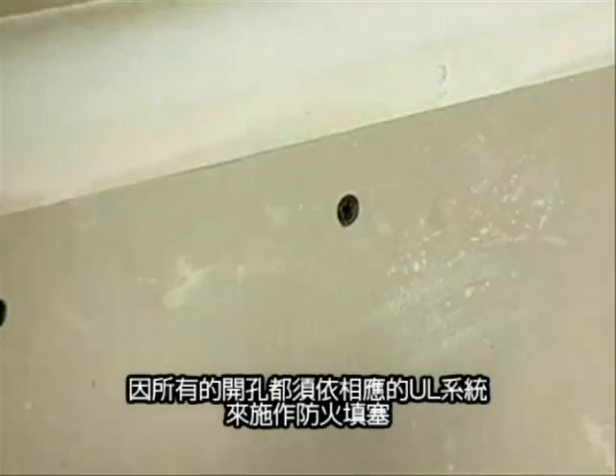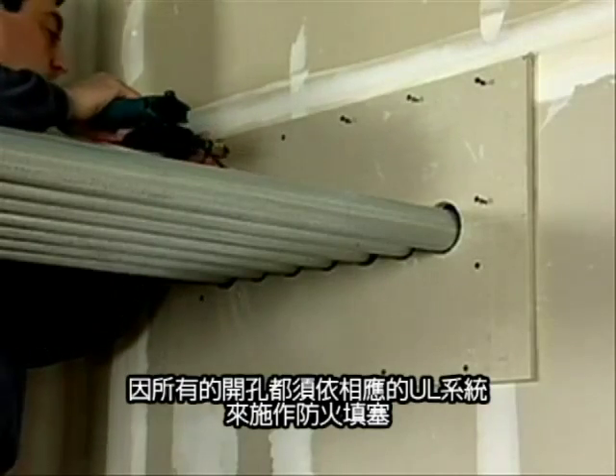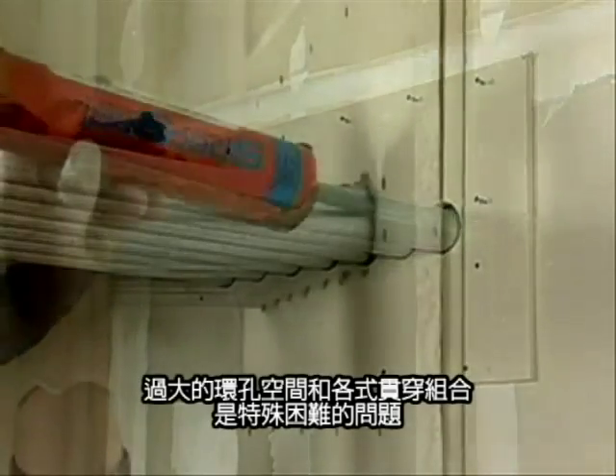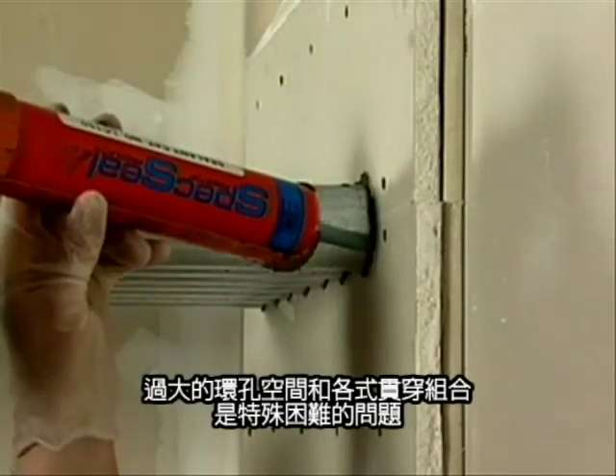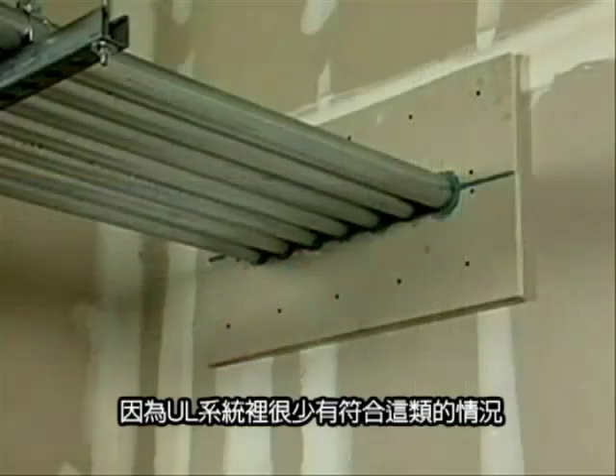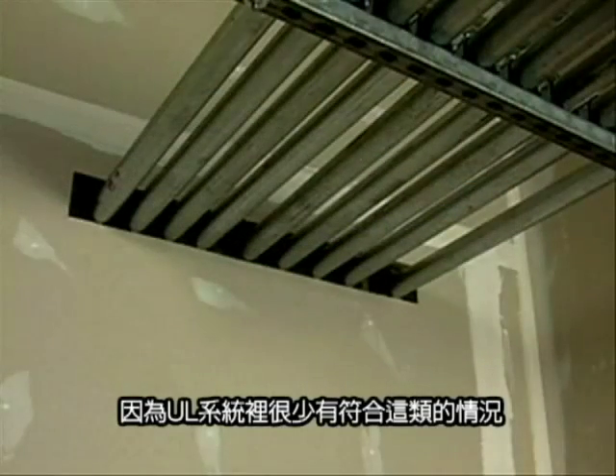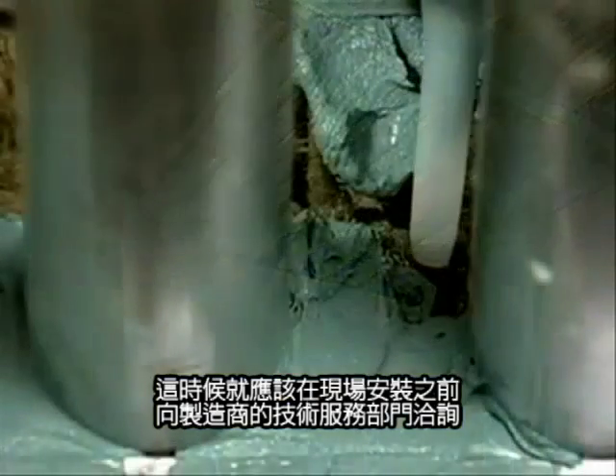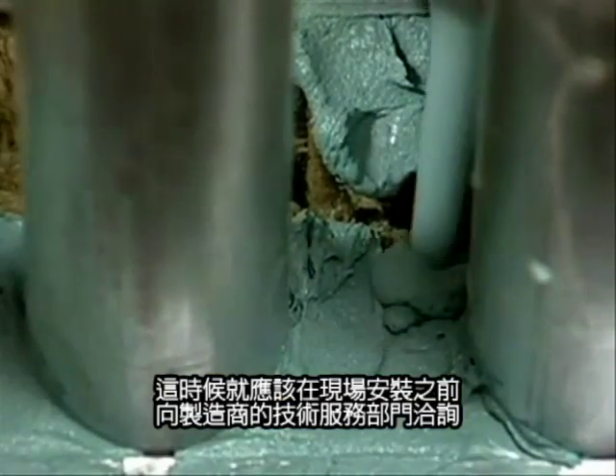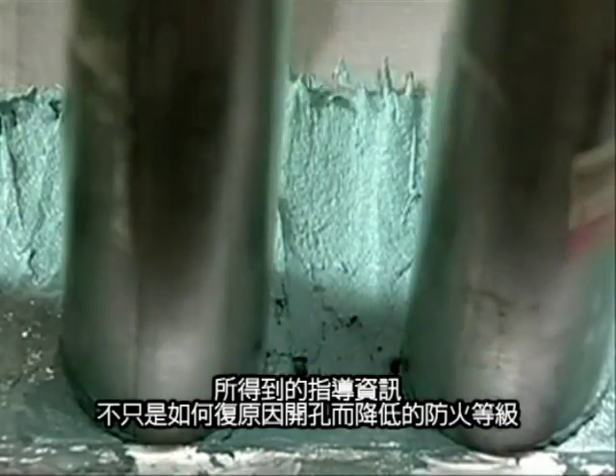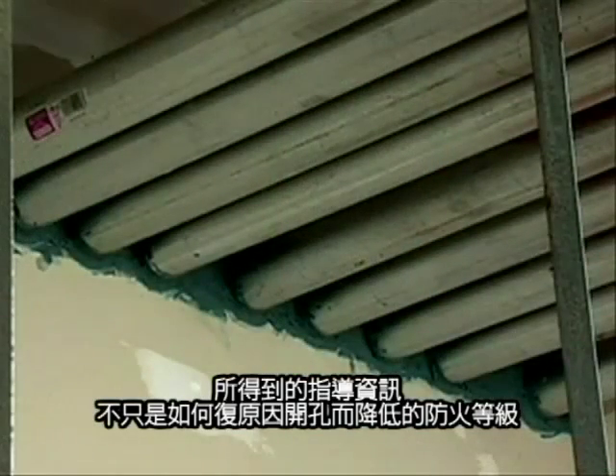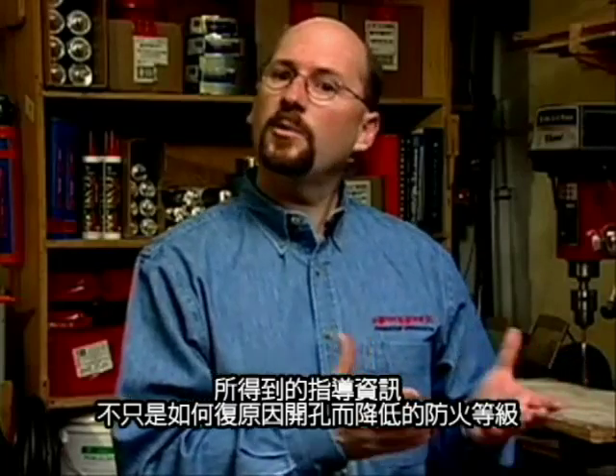While all openings must be sealed within the requirements of a given UL system, excessive annular spaces and grouped penetrations present an especially difficult problem because there are so few UL systems available for these conditions. When a UL system is not available, contact the fire stop manufacturer's technical service department for instruction prior to installation. The instructions will not only indicate how to restore the fire rating, but also how to deal with the multiple penetrations, the large opening size, and any other variables that need to be addressed.